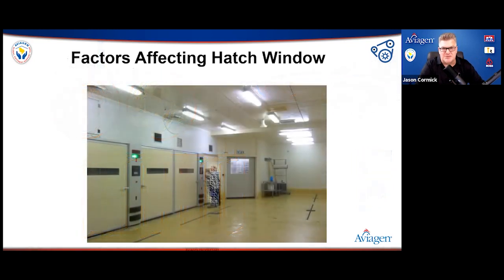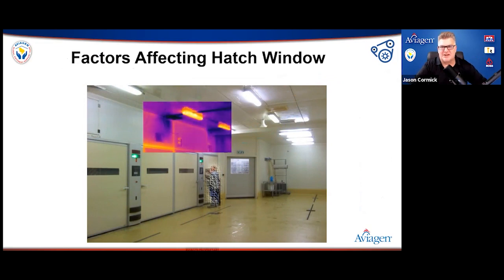Yeah, of course, we use air cooling as well. It was a very nice hatchery, but we had a problem here with this machine in the corner where you see the sort of pixelated guy standing there. It was just the air supply going to that was not as cool as elsewhere. So if you look at the machine on the left-hand side, you'll see this almost ghost image coming in. And you'll see that up here, you don't see anything. So that means you're getting more cooling air going to one machine than another.